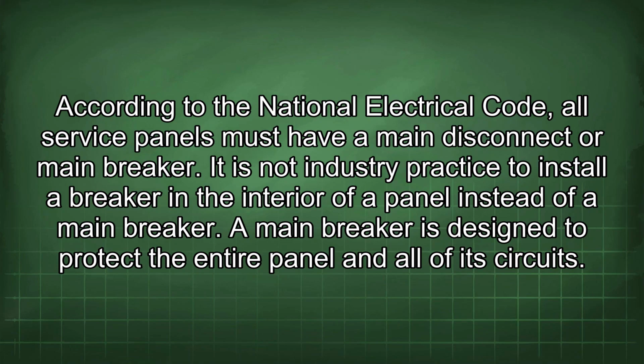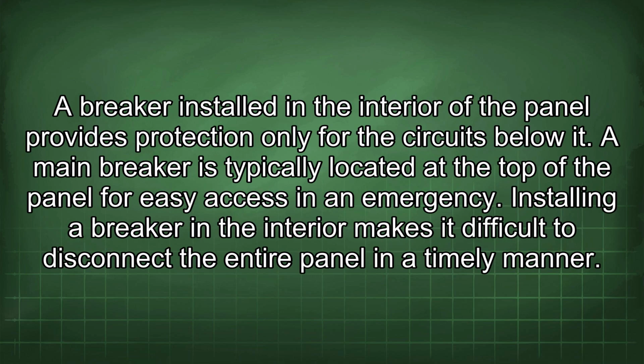According to the National Electrical Code, all service panels must have a main disconnect or main breaker. It is not industry practice to install a breaker in the interior of a panel instead of a main breaker. A main breaker is designed to protect the entire panel and all of its circuits. A breaker installed in the interior of the panel provides protection only for the circuits below it.